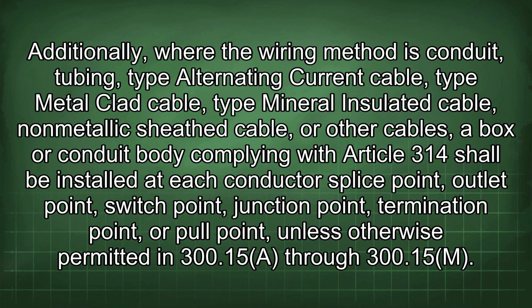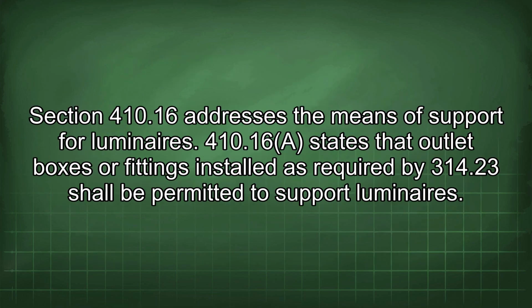Additionally, where the wiring method is conduit, tubing, Type AC cable, Type MC cable, Type MI cable, nonmetallic-sheathed cable, or other cables, a box or conduit body complying with Article 314 shall be installed at each conductor splice point, outlet point, switch point, junction point, termination point, or pull point, unless otherwise permitted in 300.15(A) through 300.15(M). Section 410.16 addresses the means of support for luminaires.